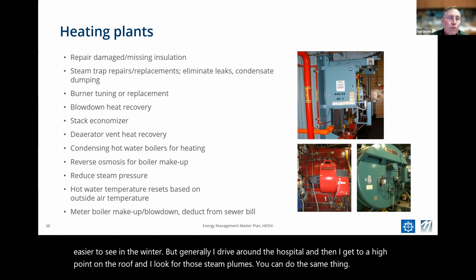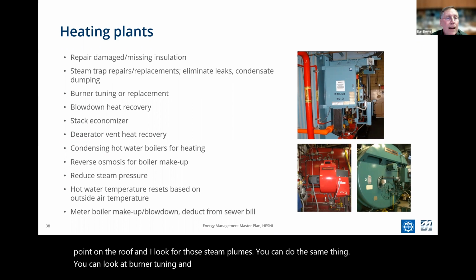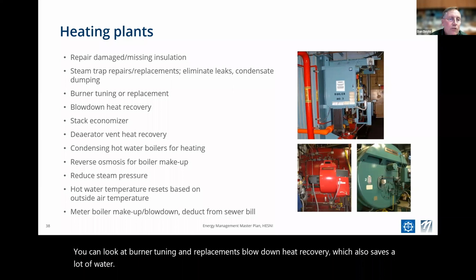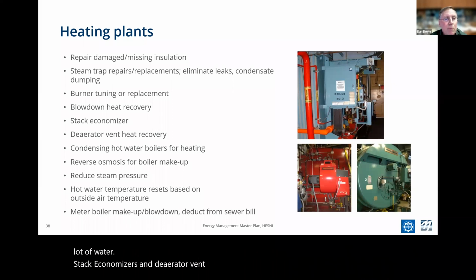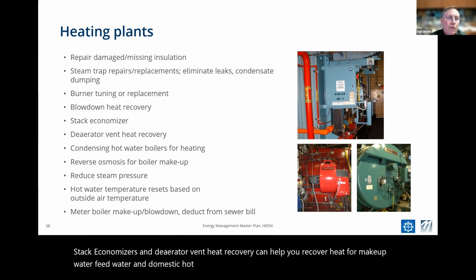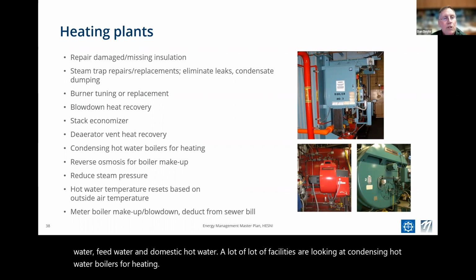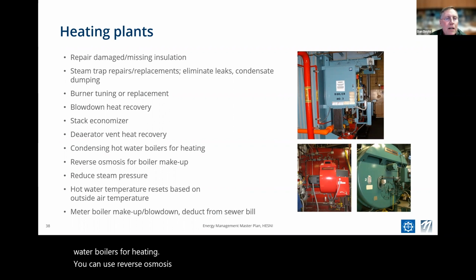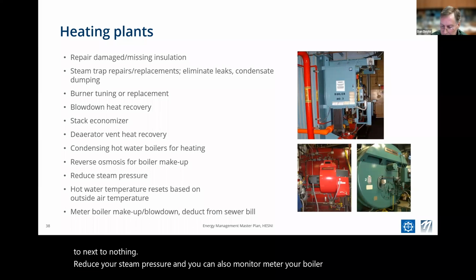You can look at burner tuning and replacements, blowdown heat recovery, which also saves a lot of water. Stack economizers and de-aerator vent heat recovery can help you recover heat for makeup water, feed water, and domestic hot water. A lot of facilities are looking at condensing hot water boilers for heating. You can use reverse osmosis systems for boiler makeup, and then your blowdown goes down to next to nothing. Reduce your steam pressure, and you can also meter your boiler makeup and blowdown and deduct that from your sewer bill.